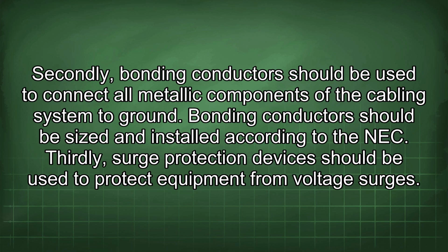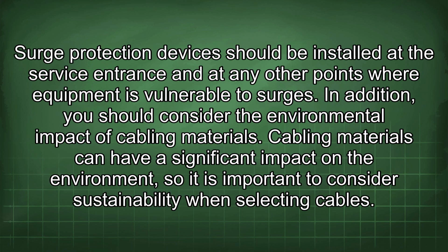Bonding conductors should be sized and installed according to the NEC. Thirdly, surge protection devices should be used to protect equipment from voltage surges. Surge protection devices should be installed at the service entrance and at any other points where equipment is vulnerable to surges. In addition, you should consider the environmental impact of cabling materials.